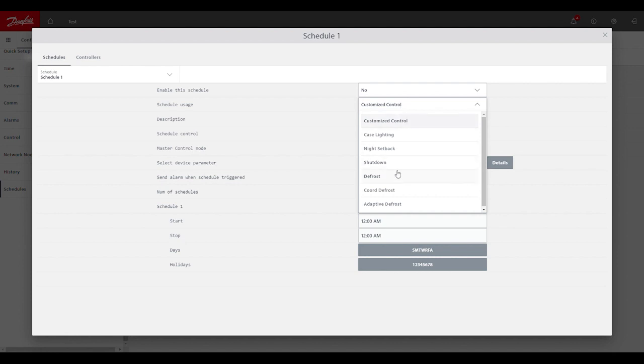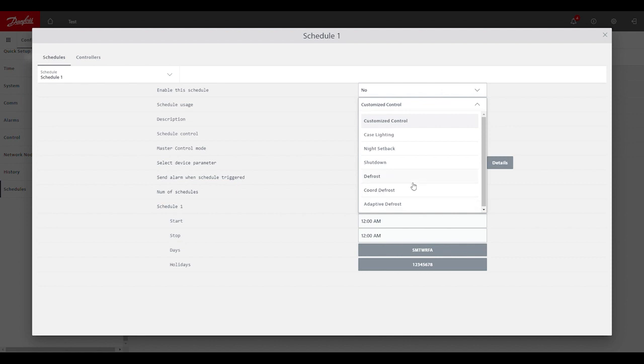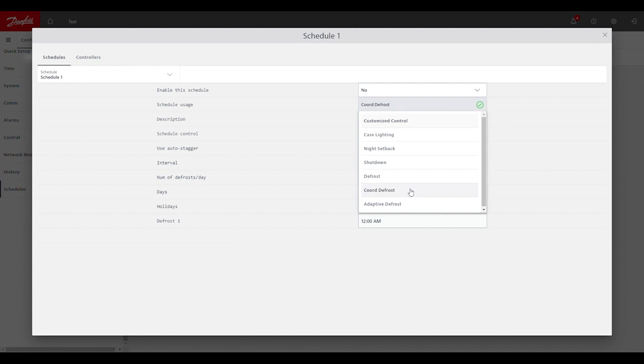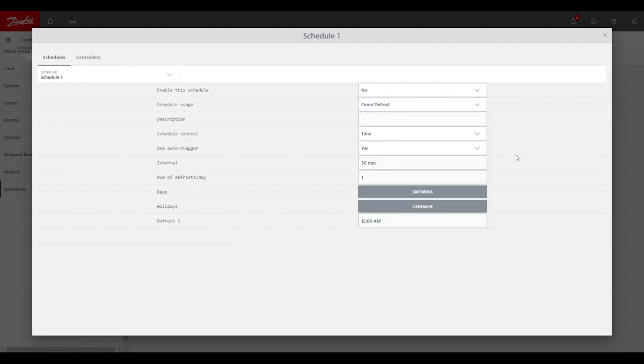Schedule usage in this case would be defrost. So we could use just defrost itself if it's just a single evap case controller by itself. If we have multiple case controllers that we want to defrost together and terminate and not go back into refrigeration mode until all the case controllers in that group have terminated, then we want to choose coordinated defrost. So one of these two options typically is what we would see used. So we'll go ahead and choose coordinated here, even though we just have the single case controller.